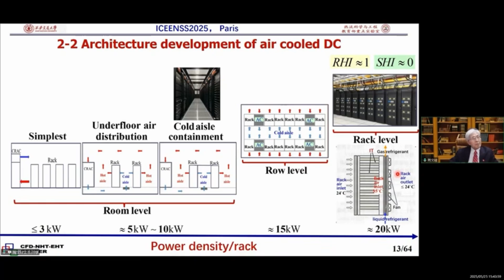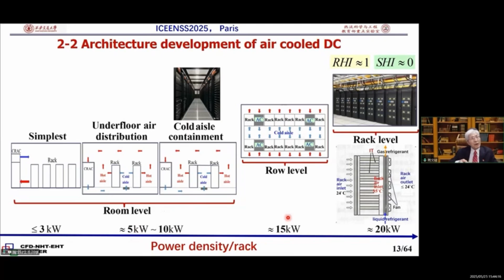As for the power density, at the very beginning, each rack was less than 3 kilowatts. And underfloor distribution is about 5 kilowatts to 10 kilowatts. And for the row level, it's about 15 kilowatts. And for this one, about 20 kilowatts.